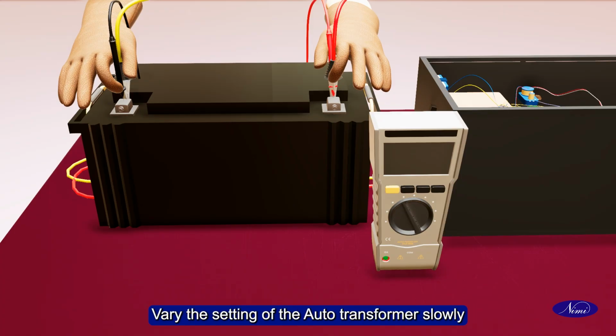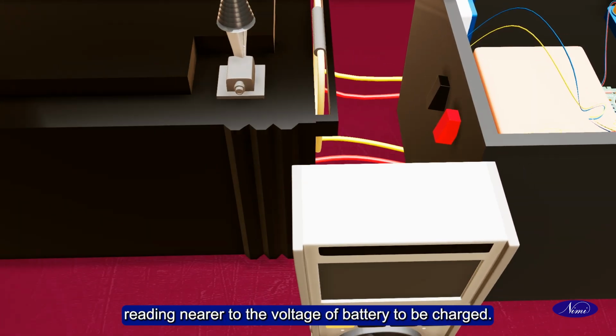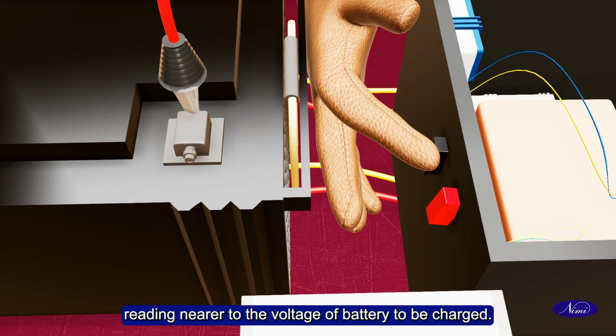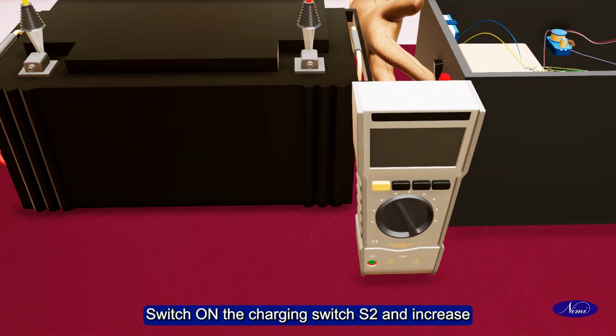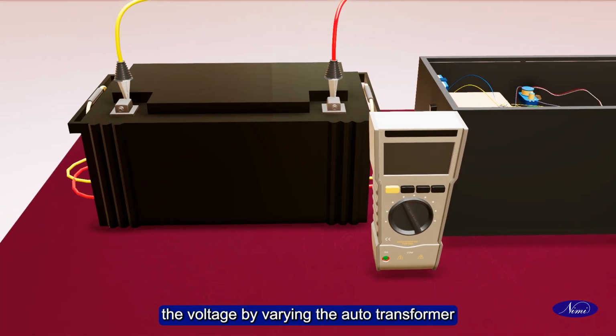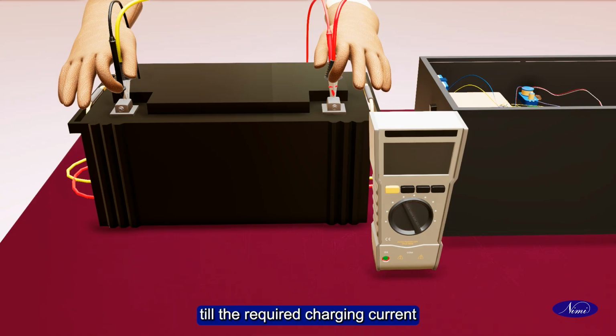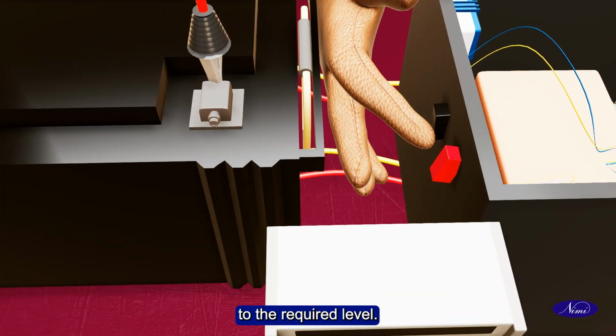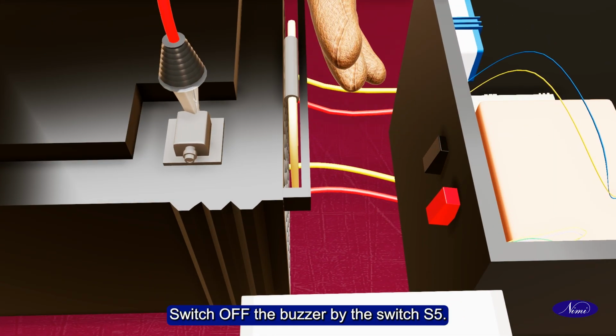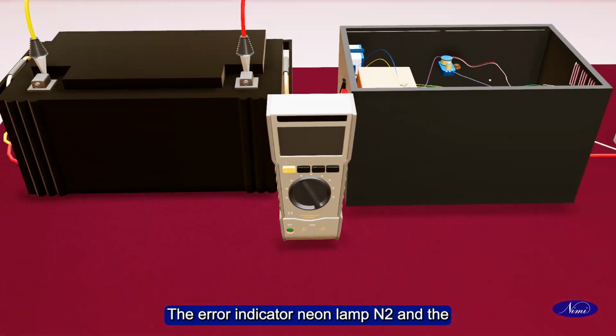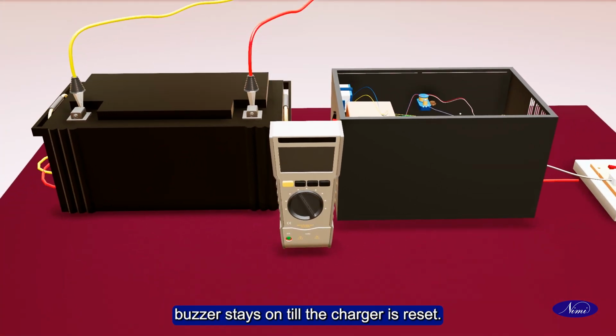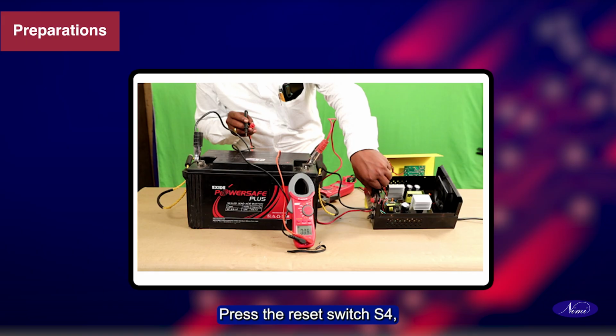Vary the setting of the auto transformer slowly from zero position until the voltmeter shows the reading nearer to the voltage of battery to be charged. Switch on the charging switch S2 and increase the voltage by varying the auto transformer till the required charging current, 5 ampere, is displayed by the ammeter. Leave the charger on to charge the battery to the required level. Switch off the buzzer by the switch S5. The error indicator neon lamp N2 and the buzzer stay on till the charger is reset. Press the reset switch S4 only if the process continues once again.